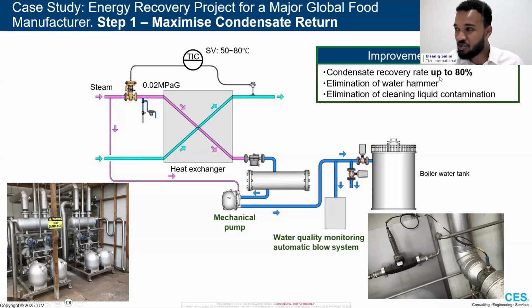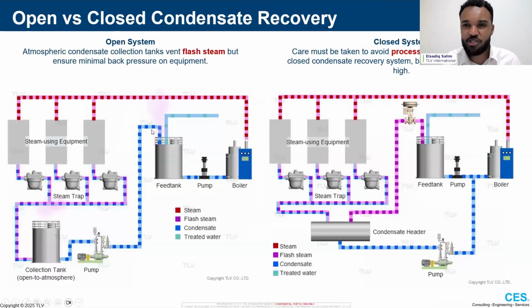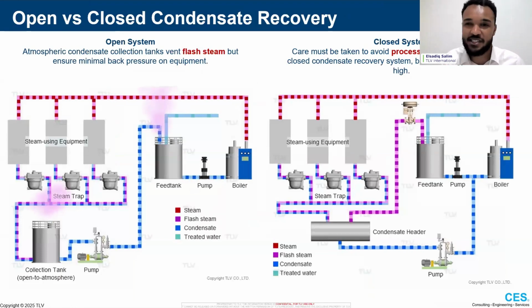But in general, most of the time, so 80% of the time or more, it was clean. It was deemed clean enough to return to the boiler, because it's only an issue if there is a rupture in the heat exchanger anyway. So implementing this across site, we can see some of the pump sets over there, took the condensate recovery rate up to 80%, also eliminated water hammer cases in their heat exchanger, and prevented or mitigated the risk of cleaning liquid contamination. And we'll discuss detail about the payback period a bit later, because there's a second project on this same site.